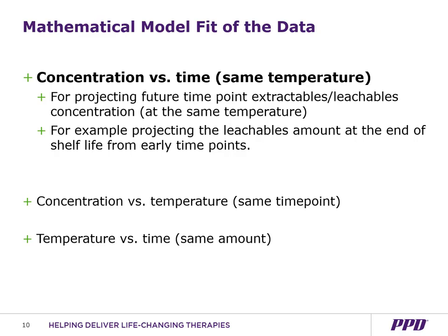I'll start with concentration versus time, where we are looking at projecting future time point extractables and leachables at the same temperature. Having this model would allow us to project the leachable amount at the end of a shelf life based on data from earlier time points.